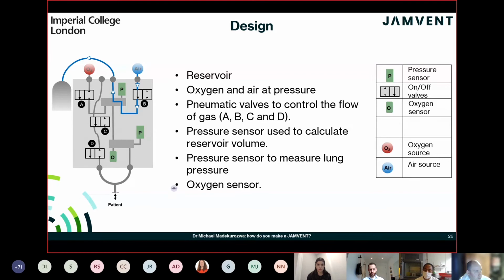There's an oxygen sensor inside the system down over here, which measures the actual oxygen to air concentration that's being delivered to the patient. And there are also pressure release valves inside the system. The pressure release valves are over here and over here. These help make sure that the system pressure doesn't go too high as a safety mechanism. So ventilators usually have a lot of safety mechanisms inside of them because as Dr. Mathiszig-Lee mentioned earlier, there's a lot of safety that has to go into these devices as the lungs are very, very delicate organs.